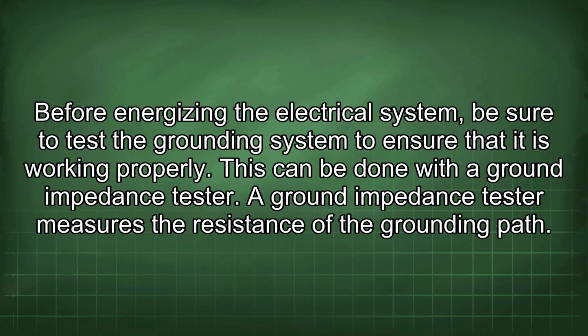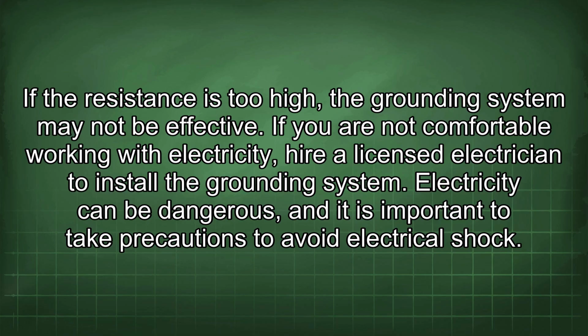Before energizing the electrical system, be sure to test the grounding system to ensure that it is working properly. This can be done with a ground impedance tester. A ground impedance tester measures the resistance of the grounding path. If the resistance is too high, the grounding system may not be effective.